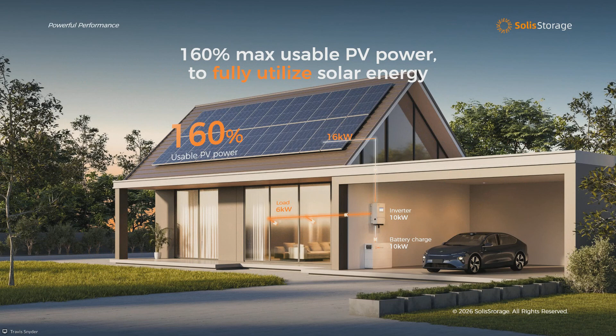All of our inverters have this max usable PV power. Just because an inverter says it's a 10 kilowatt inverter doesn't mean it can't process higher power. Say I have a Solis 10K, it can actually charge the battery at 10 kilowatts and also send 6 kilowatts to the load. So it's technically 16 kilowatts internally, but it only can inject 10 kilowatts to the grid. That's one huge selling point and benefit of the Solis.